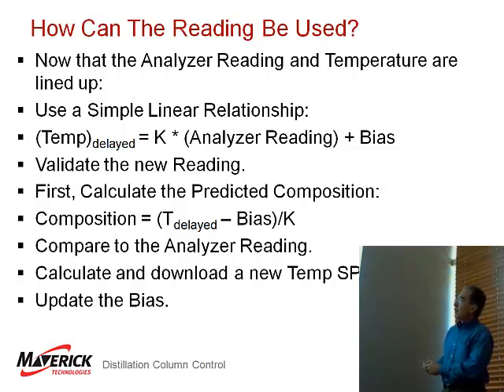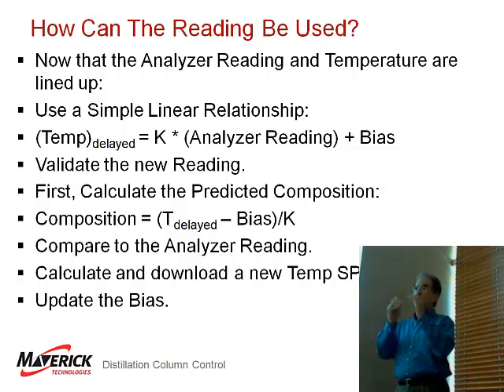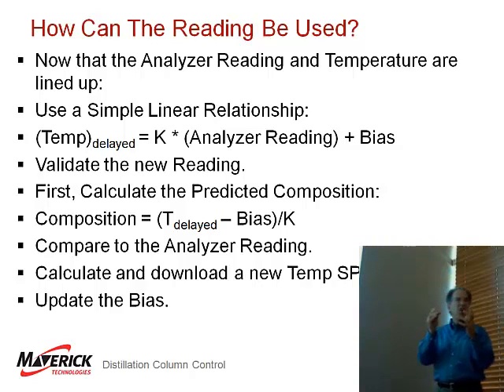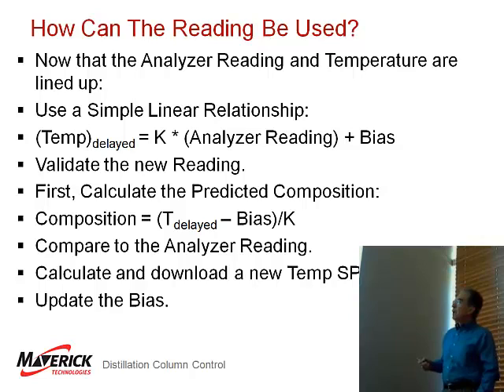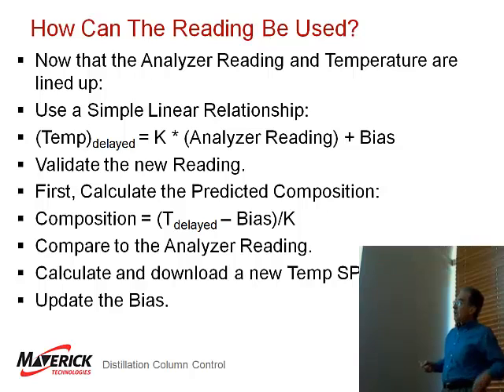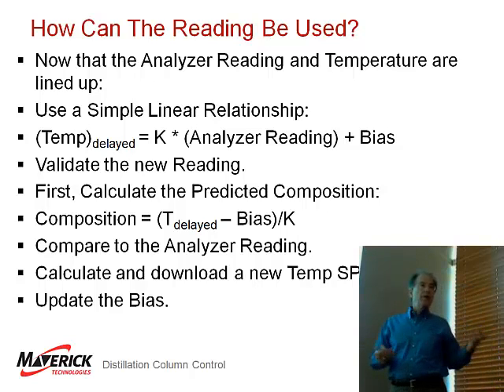Once validated, you calculate the predicted composition from the equation by inverting it, then compare it to the analyzer reading. You have rules to decide whether to use PID or just integral or gain action. Either way, you use some kind of feedback control based on the analyzer reading and the predicted composition, then calculate and download a new temperature set point and update the bias in the simple equation. That's how you use process identification.